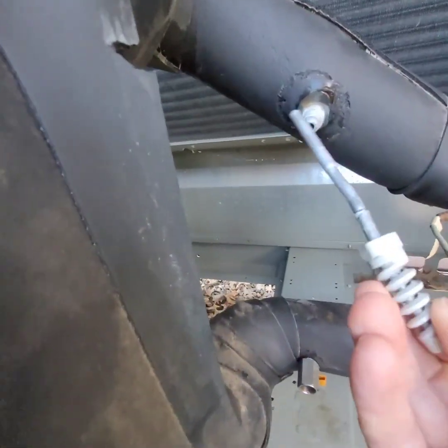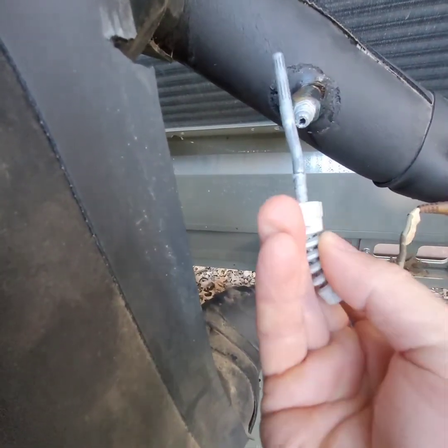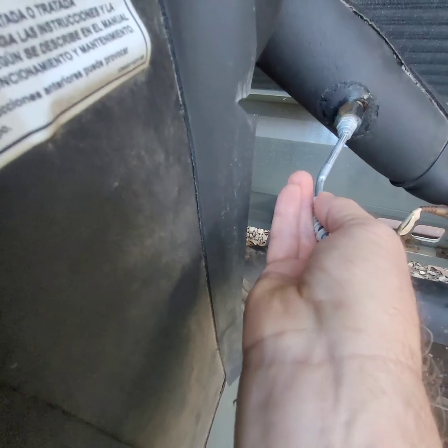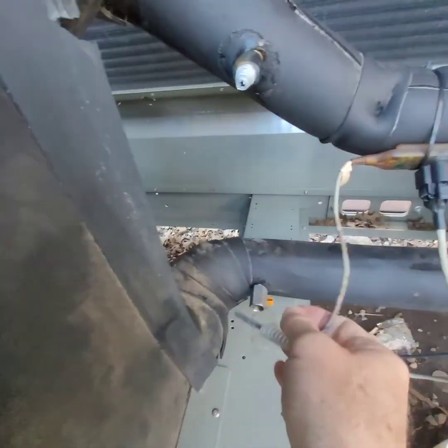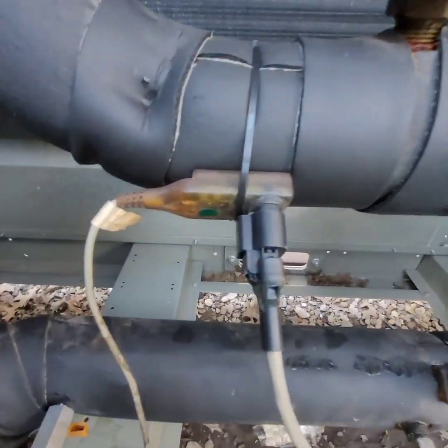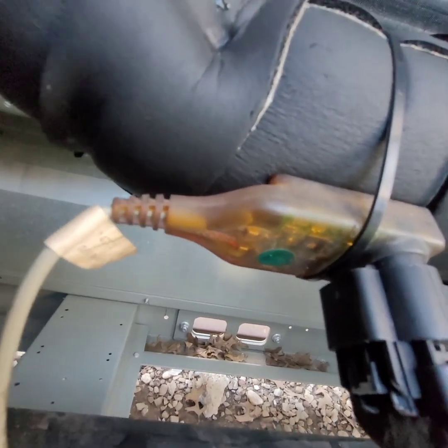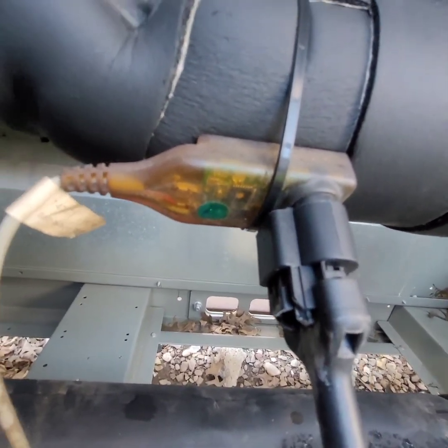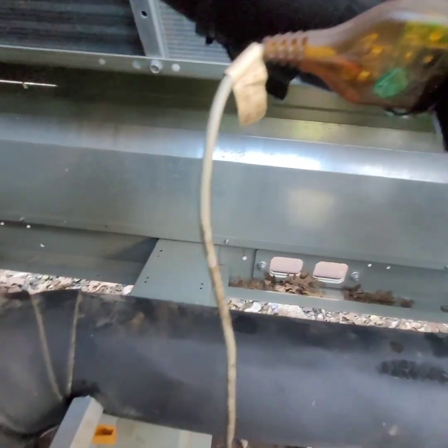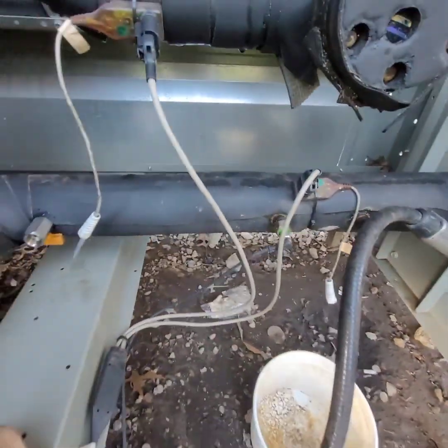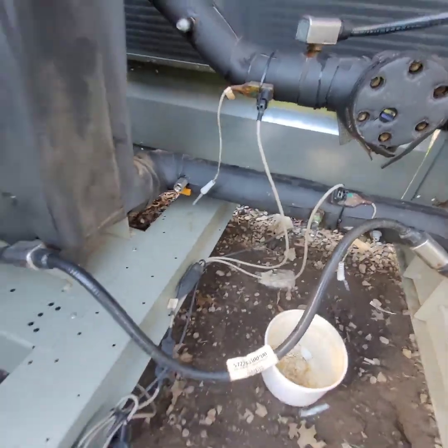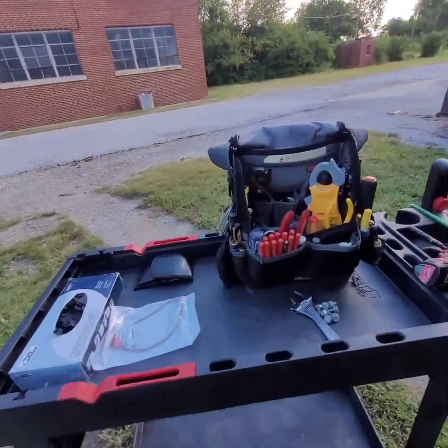Anyway, these sensors, they go right in these little wells right here. It's got nevr-seez all over there, so it's pretty messy. But anyway, they go in there. And they do have these electronic sensor modules that you have to bind with the Trane software. Those aren't available right now. I can't get those. This chiller won't run. So I'm going to go ahead and try to splice in a sensor.